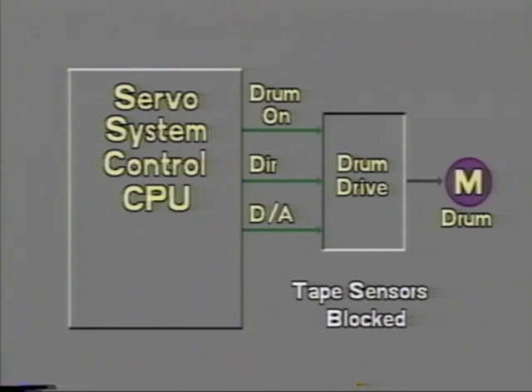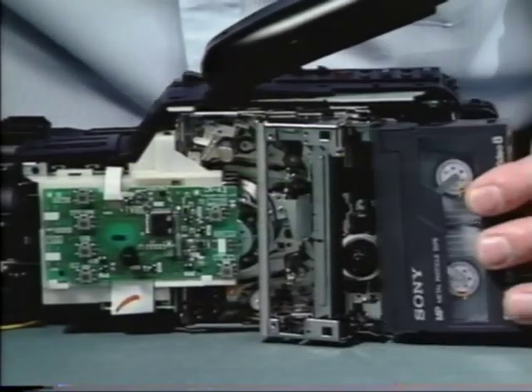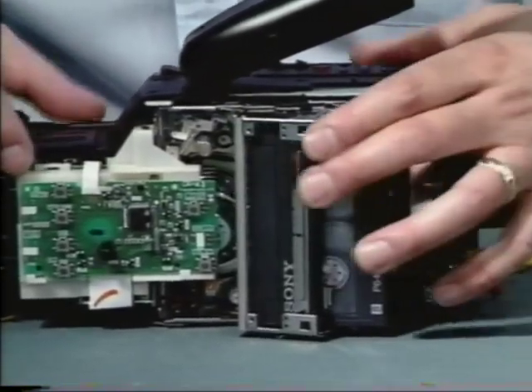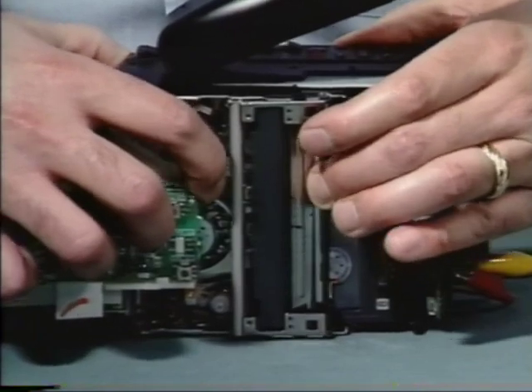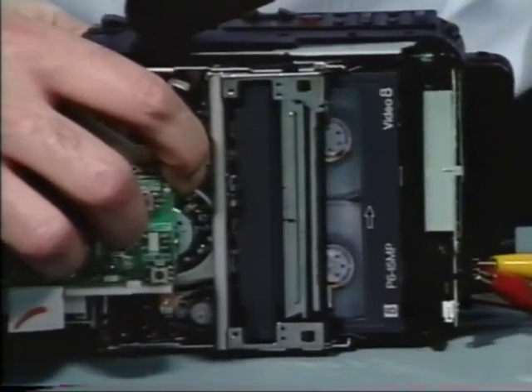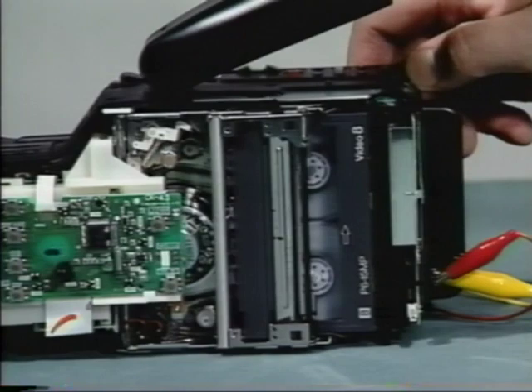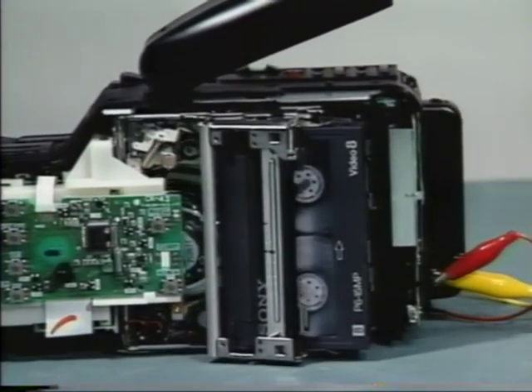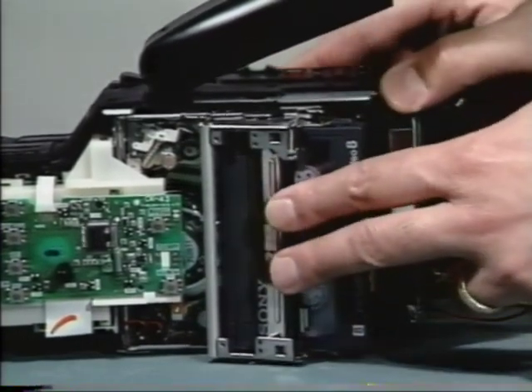Once in the spin-up mode, the servo system control CPU looks for the drum's PG pulses to be present. If the PG pulses are not detected within 4 seconds of the drum-on signal, the loading process is immediately aborted and the servo system control CPU enters the emergency shutdown mode. At this point, the tape can only be ejected and the loading process can then be reattempted.